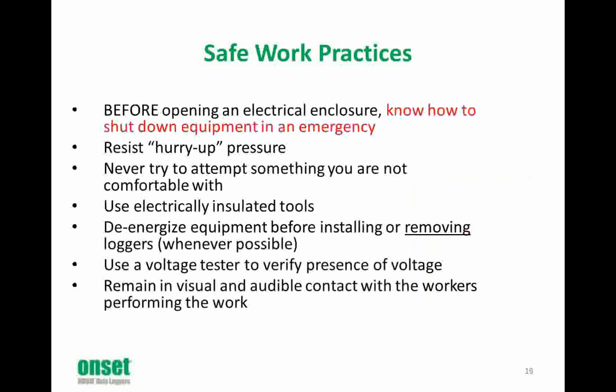Before we open an electrical enclosure, it's important that we know how to shut down the equipment in the event of an emergency. We always want to resist hurry-up pressure. We never attempt something that we're not comfortable with. We only use electrically insulated tools inside the electrical equipment. And whenever possible, we want to de-energize the equipment before making our installation or removing data loggers.